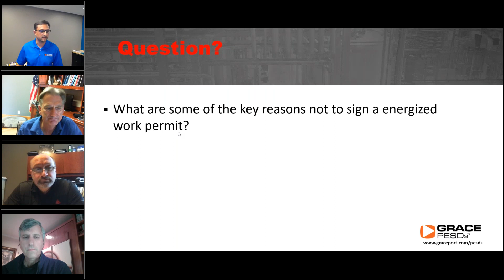Anu, can I just comment that I think some people forget that in 70E and Z462, there are some exemptions where you don't need the permit, right? Yes. What I find is that quite a few people believe they need an energized electrical work permit for every energized electrical work task. That's not true. There are exemptions documented in 70E and Z462. And really the reason for the exemptions is that it's infeasible to do it de-energized due to equipment design, right? So there are valid reasons when the energized electrical work permit should be exempted and is not required. So I just want to add that it is not required for all energized electrical work tasks. Correct. No, absolutely correct. Thanks for bringing that up. Absolutely.